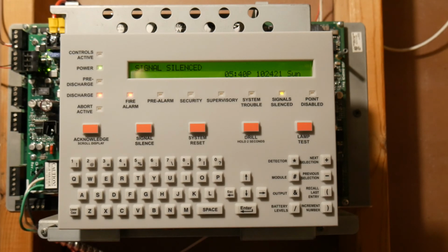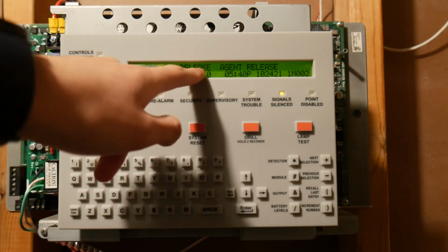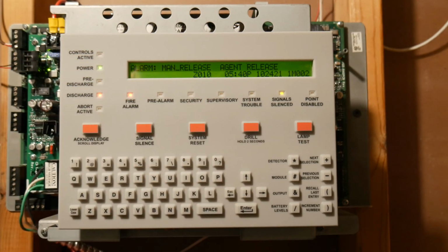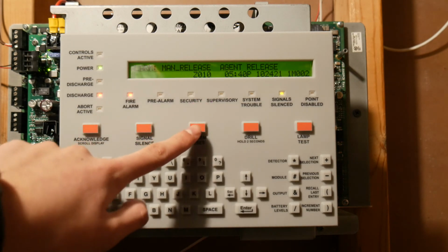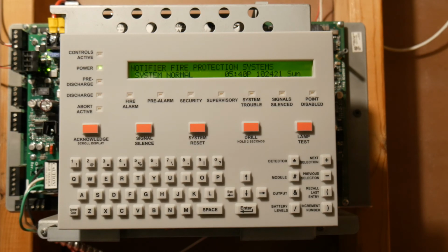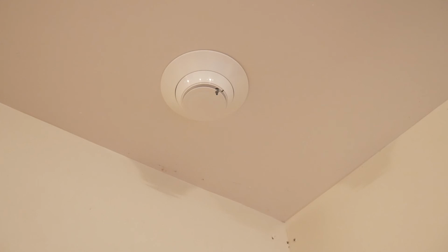Okay, so as you can see, it says discharge. It says manual release, agent release, zone 10. And it only activated the Gentex Commander and not the other NACs, which is really good because that's what I wanted it to do. So press system reset. It's back to normal. And then I'll test a detector.